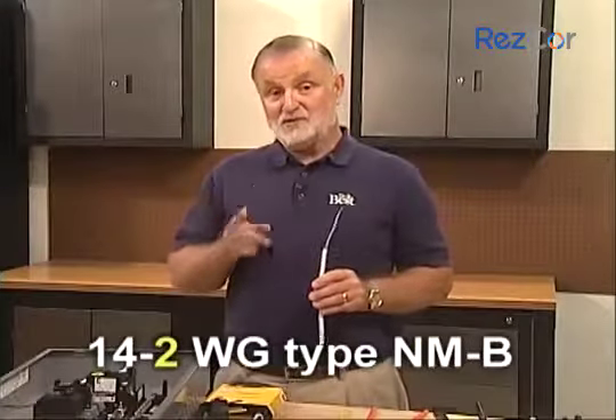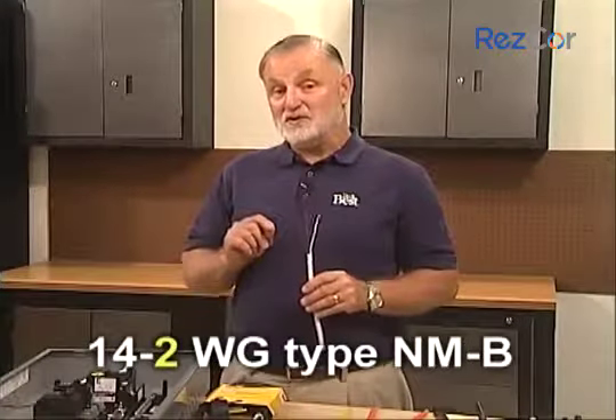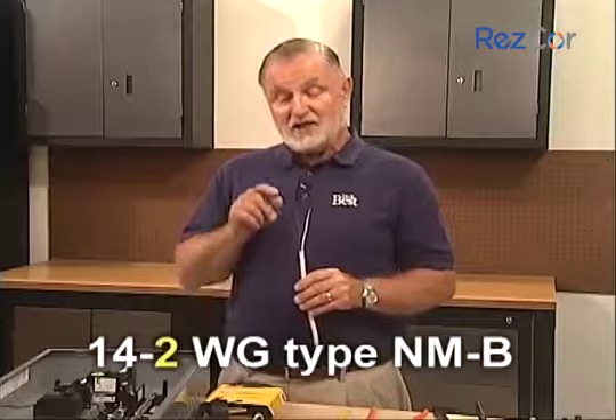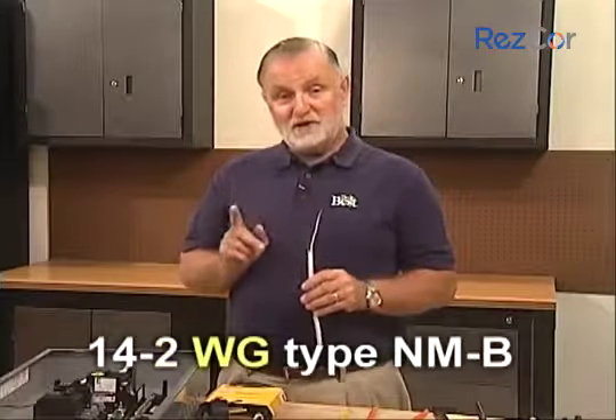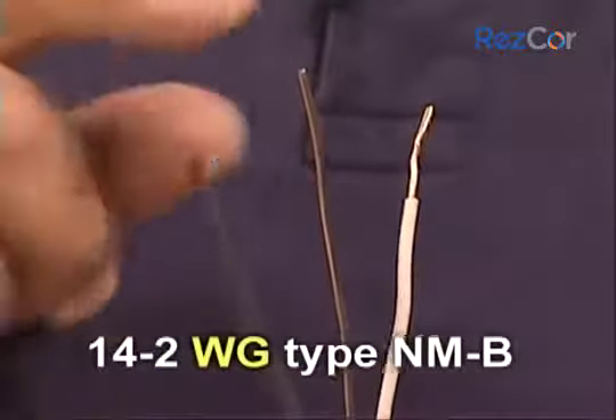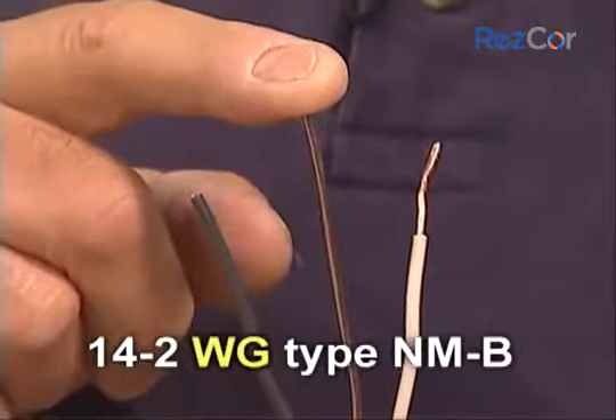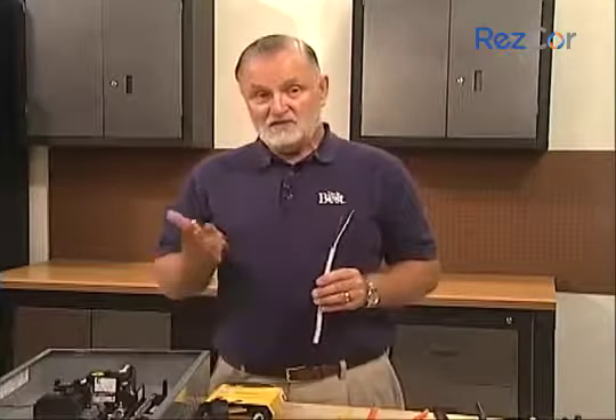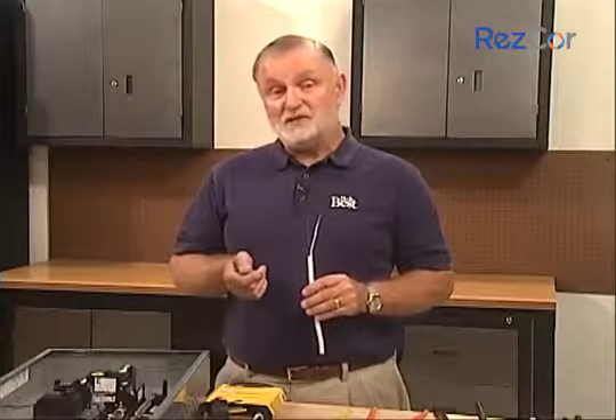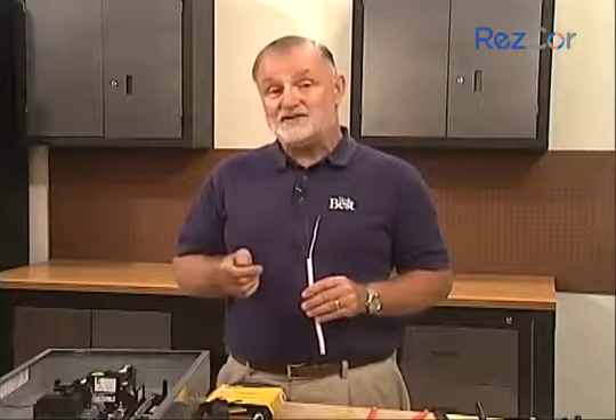The second number, the 2, represents the number of insulated conductors in the cable. The WG stands for with ground, which means that the cable has a bare wire in it that connects to a metal piece on any electrical component that could accidentally contact electricity, such as a metal box or a metal strap on a switch or receptacle. This helps protect you from electrocution if current accidentally leaks to the metal surface.